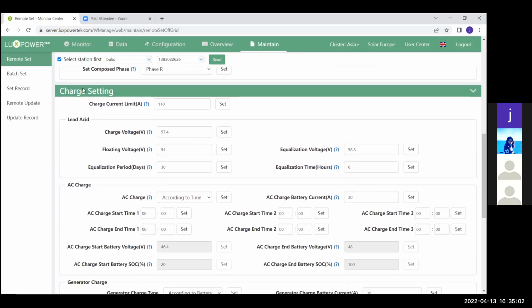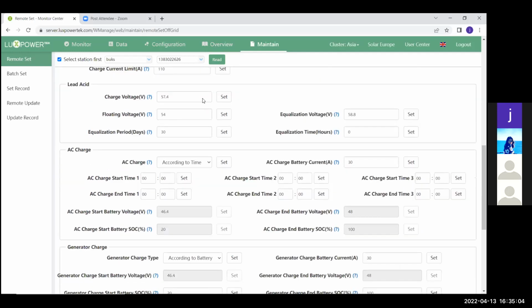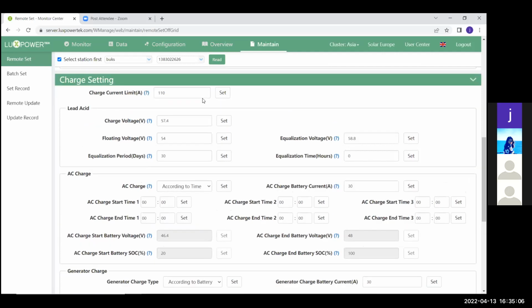From here on, you'll see our charge settings. Now at charge settings, this is the amount that your system will charge from any source. So that means it's the PV, the AC combined. It won't go higher than 110 amps. Now for a system that's communicating, it is not necessary to put this charge current limit, because the BMS will limit the amount. But I always like to be on the safer side.